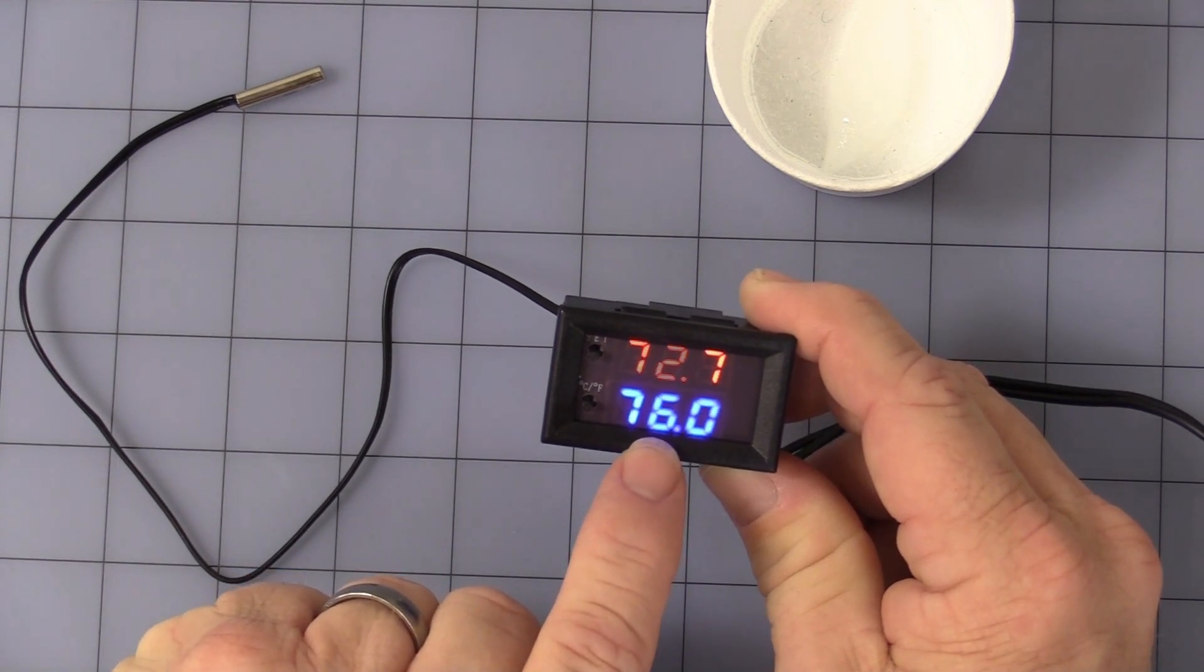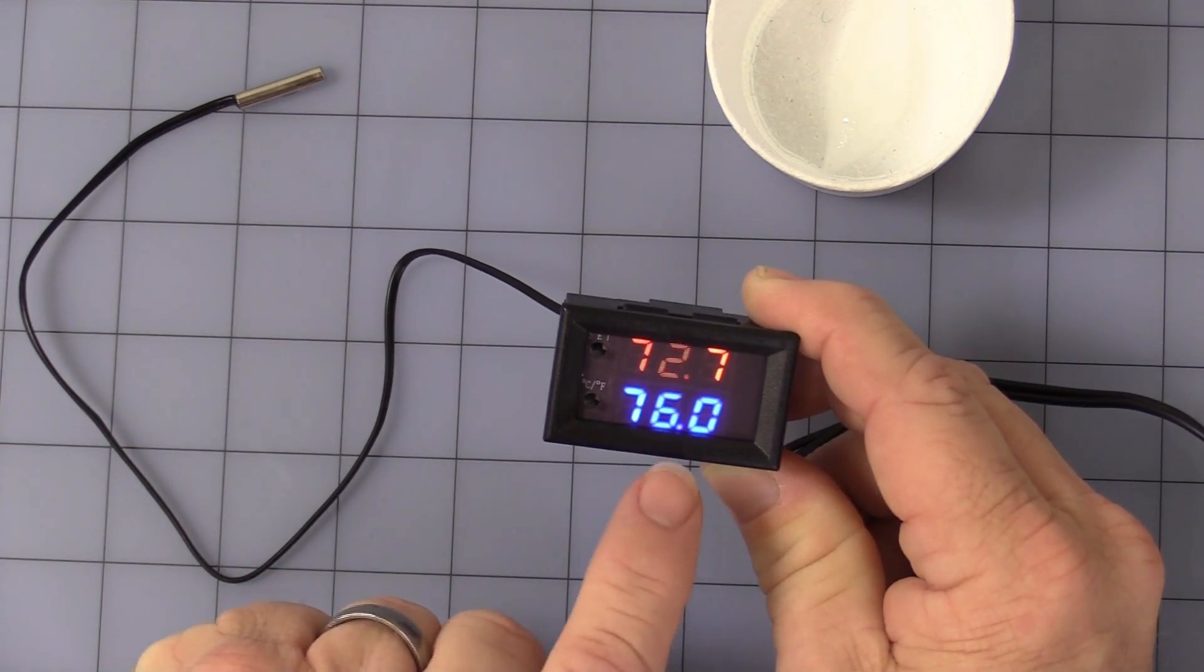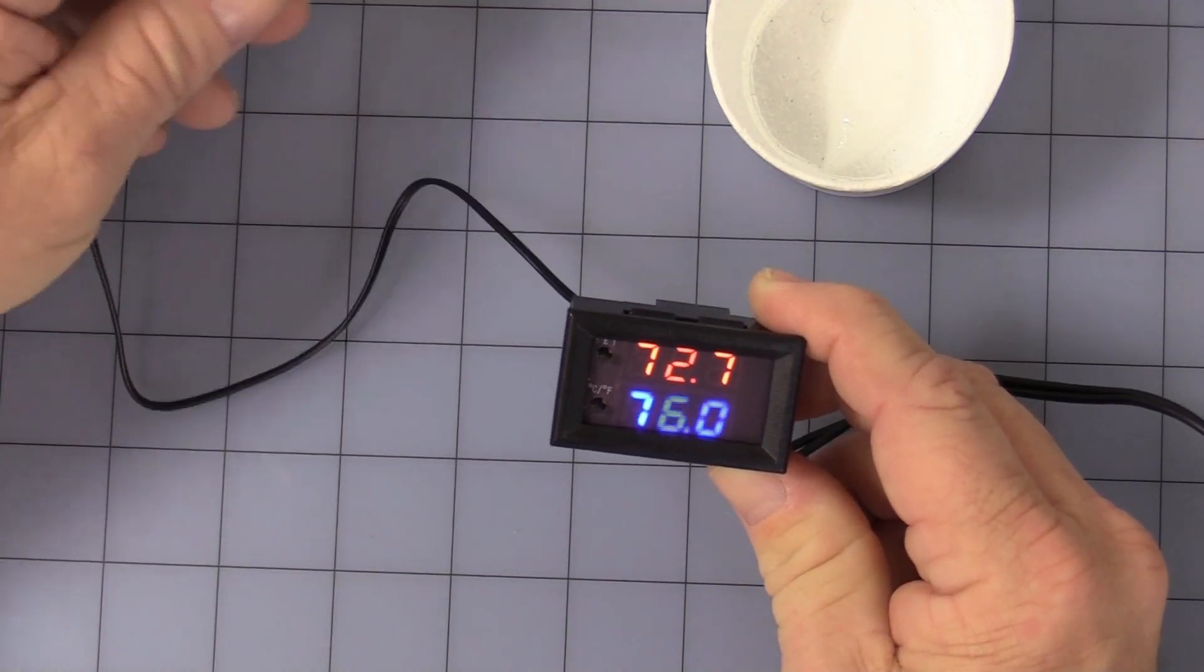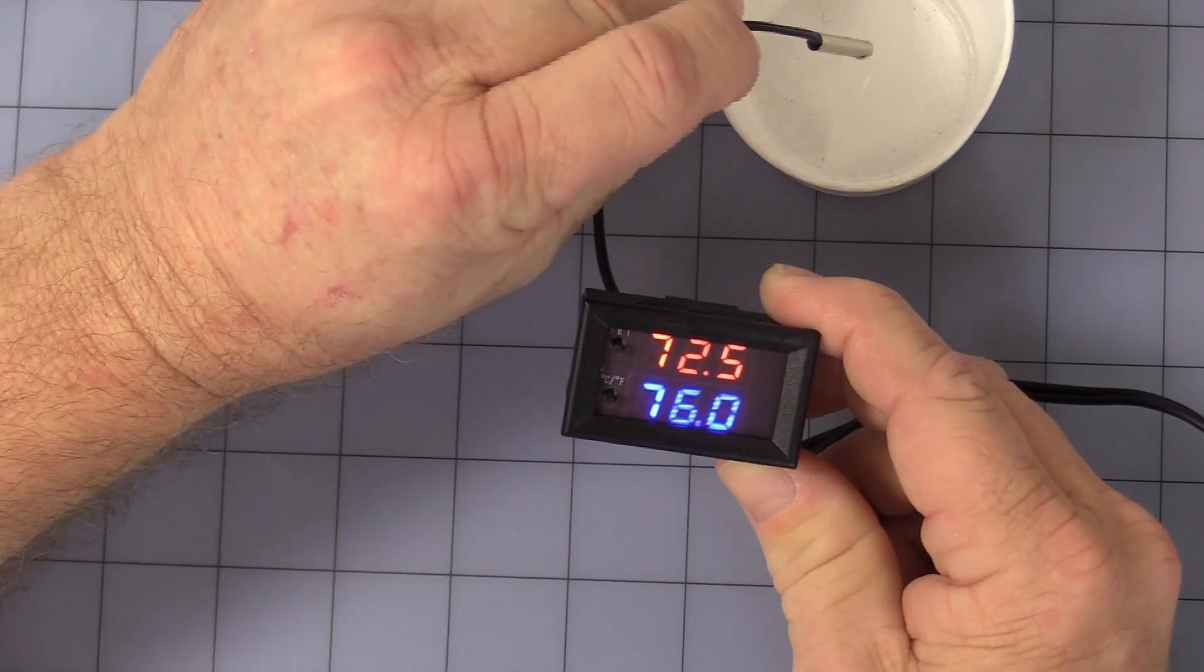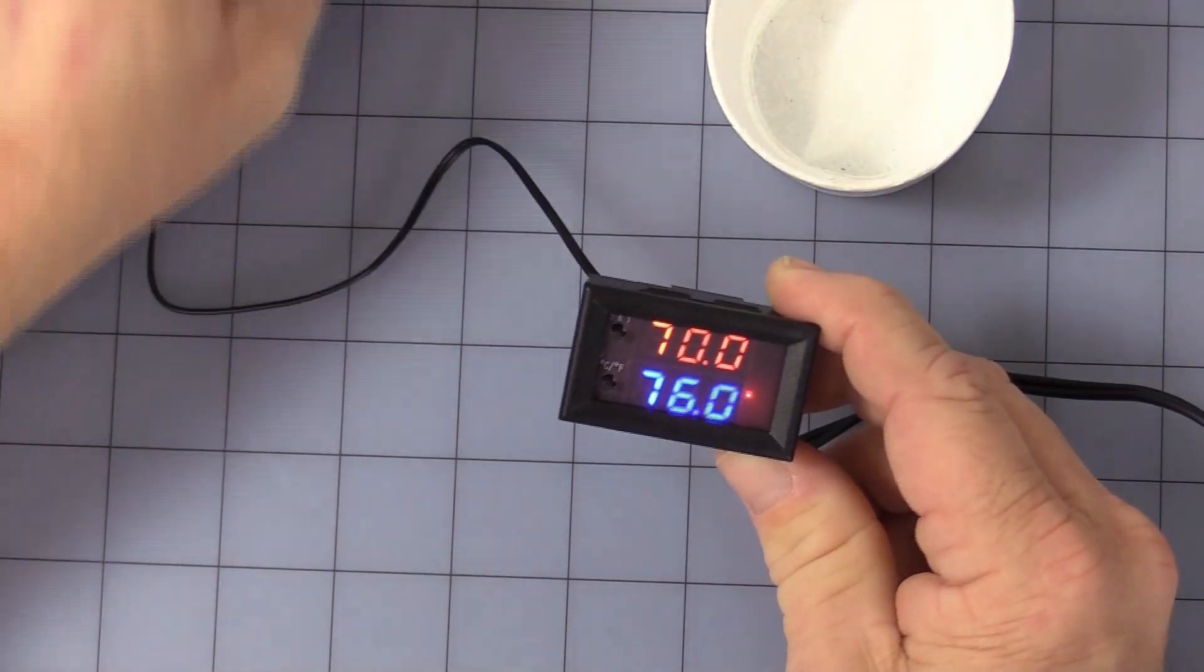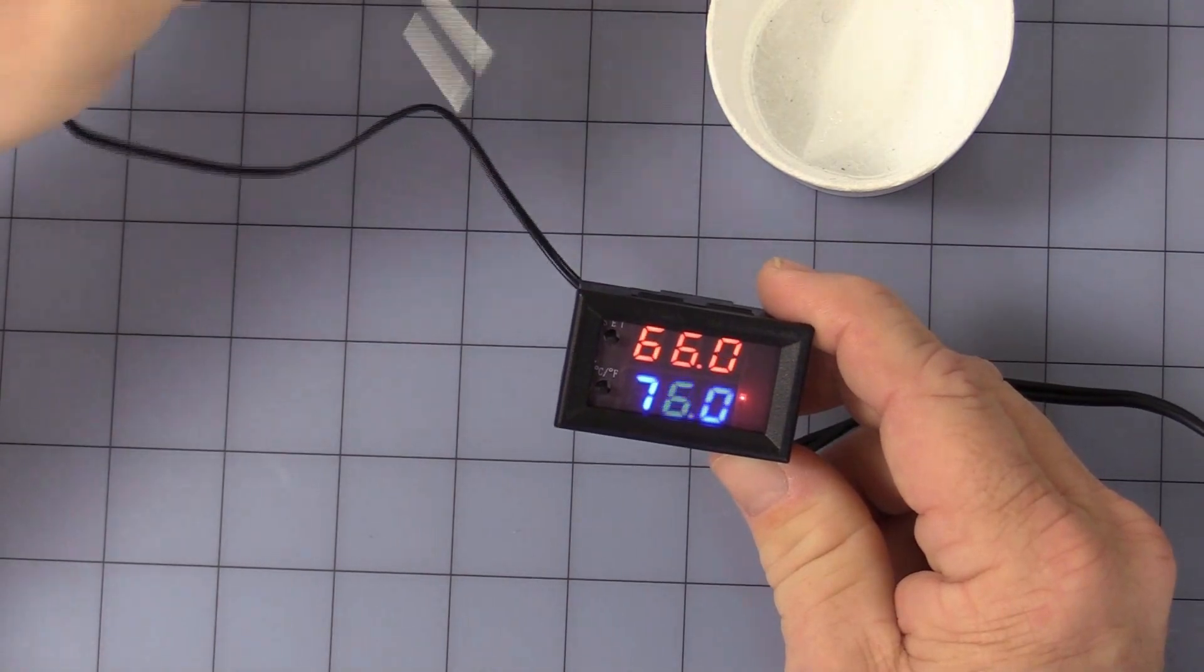So, at this point, it will probably have to get down to about still the 3.5, 3.6 degree hysteresis. We'll have to cool the sensor just a little bit to get the relay to turn on. See, the relay turns on.